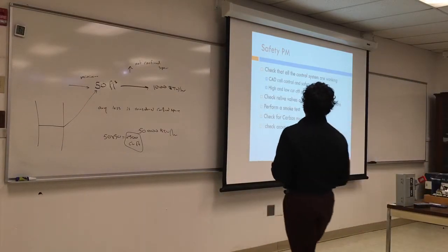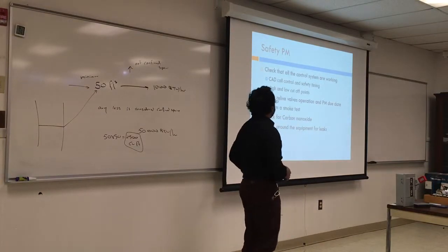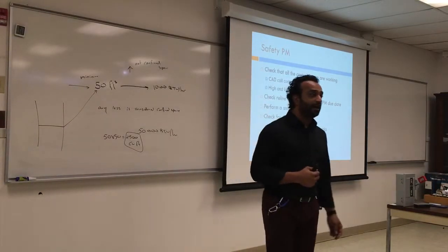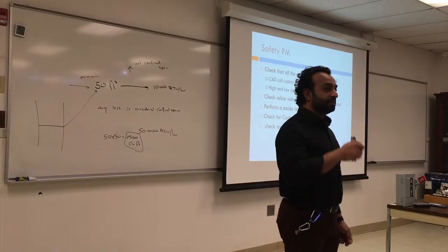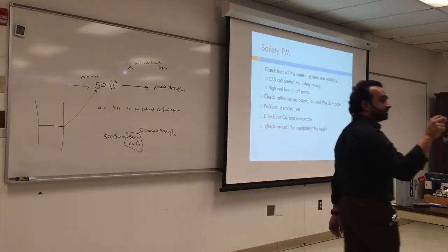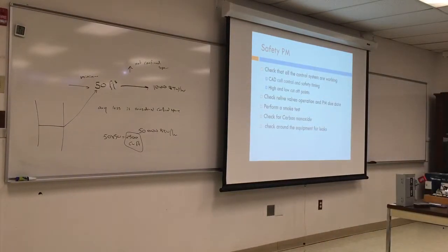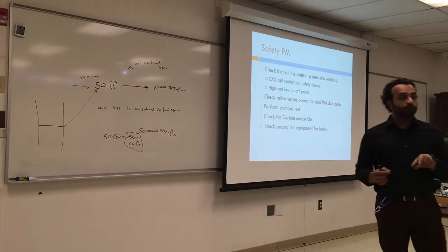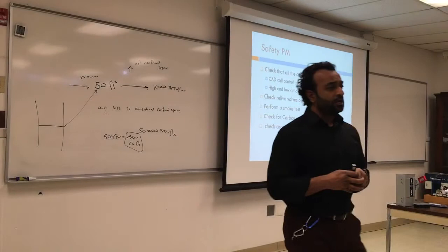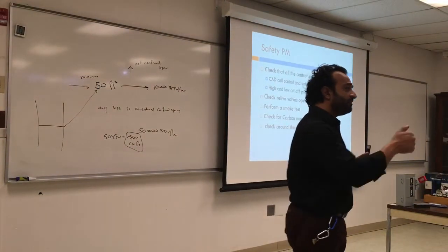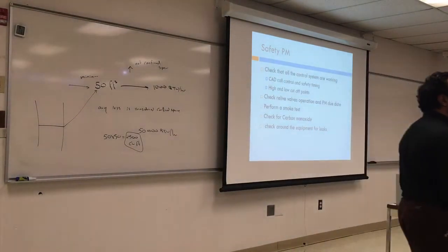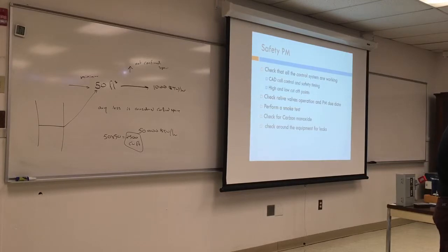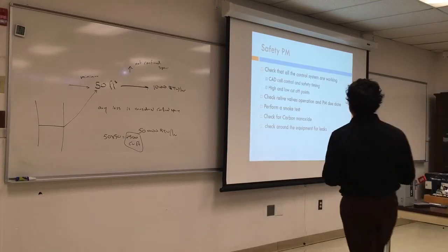So Safety PM, you want to check that all the controls are working. The CAD cell is cutting off on high limit. So when you set if it's hot water, you set the high limit and make sure you monitor the temperature and make sure the system runs on high, cuts on high limit. When you want to test your primary control, you want to cover the CAD cell and wait for it. It's going to run. It should cut out in 15 seconds. If it doesn't, something's wrong with the CAD cell control.